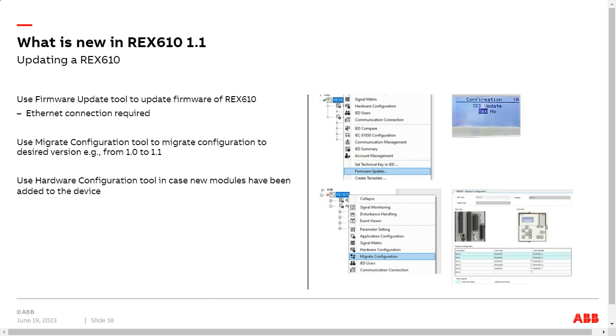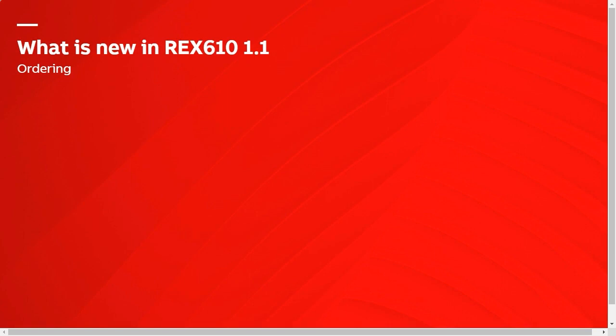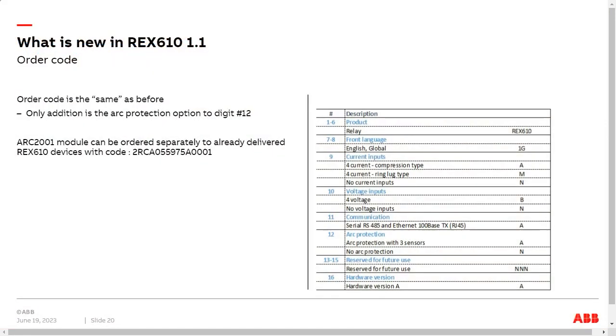Then I think I have one more slide, and that's about the ordering of the REX610, because I keep saying that there are a few variants, and we introduce new modules. Well, the order code is the same as before. The only addition is the ARC protection at this number 12. So if you now order the device, you will have the exact same order code as before. You basically inform us at the factory which hardware modules you want installed in the device. Do you want what CT module, what voltage module? Do you want ARC protection installed into it? Yes, no.